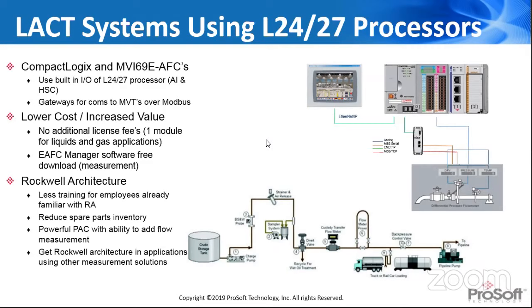Then you pass that information over the backplane to the coprocessor module, and it sits there and does the API calculations, then passes that result back to the PLC. So instead of having two different controllers, or a controller and a measurement solution on a skid, and having to network the data back and forth between the two, it's all in one platform, so it allows you to get all the information that you need.